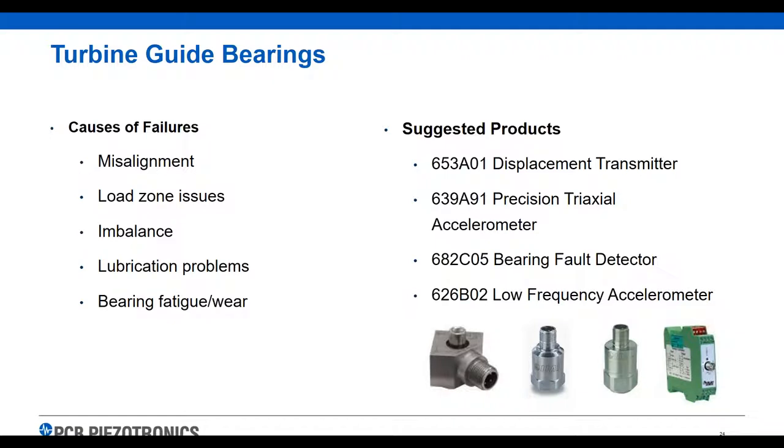Turbine guide bearings: when a customer comes to us without any vibration monitoring and asks what we suggest, turbine guide bearings are the most common thing they want to monitor first. We're looking for misalignment, load zone issues, lubrication issues, bearing problems, and imbalance. We have different types of products for this: low frequency accelerometers, bearing fault detectors, and triaxial sensors. A lot of people are starting to use triaxial sensors to get three axes of vibration with one sensor, which is very useful. Transmitters can interpret that data and feed it back into a PLC.